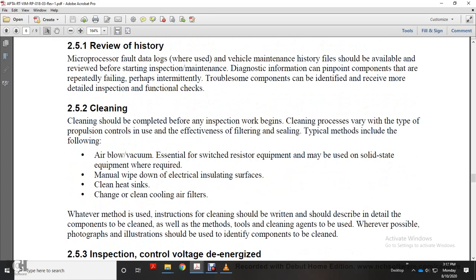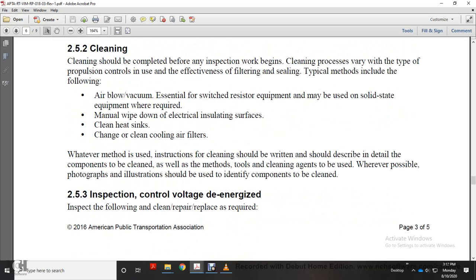2.5.2, cleaning. Cleaning should be completed before any inspection work begins. The cleaning process, with any type of propulsion control in use, depends on effective filtering and sealing. Typical methods include air blow, vacuum, and, except for solid state equipment where required, manual wipe down of electrical insulating surfaces, cleaning heat sinks, and changing cooling air filters. Whatever method is used, cleaning instructions should be written and should describe in detail the components cleaned as well as the method, tools, and cleaning agents to be used. Where possible, photographs and illustrations should be used to identify the components to be cleaned.